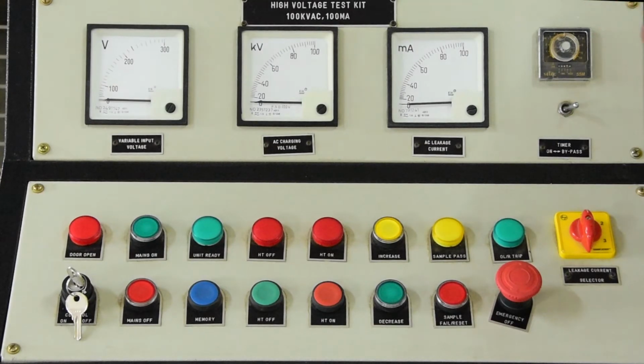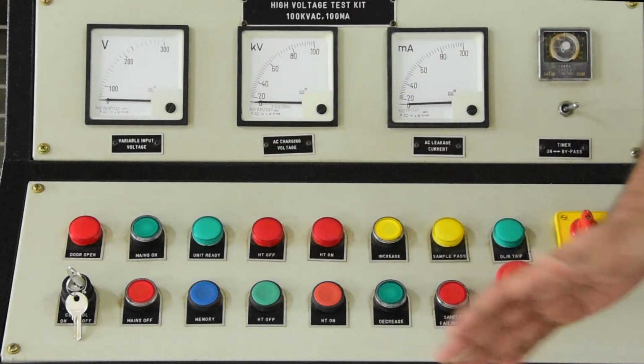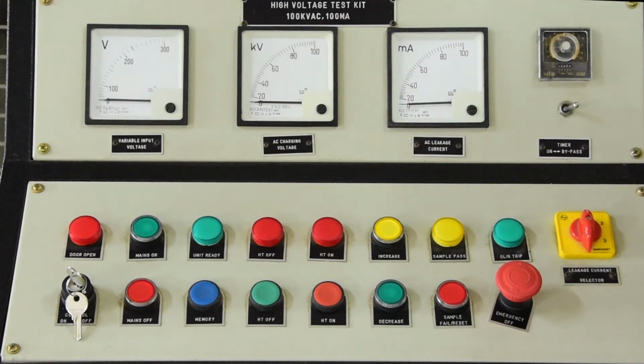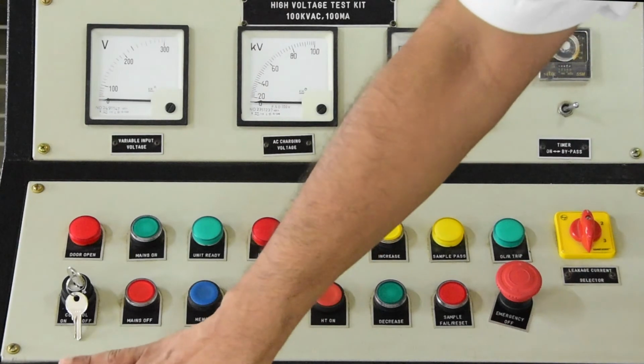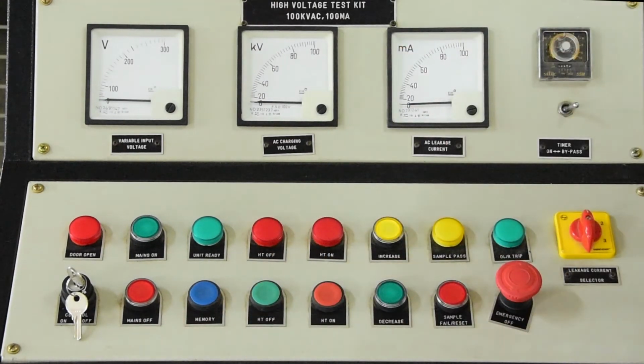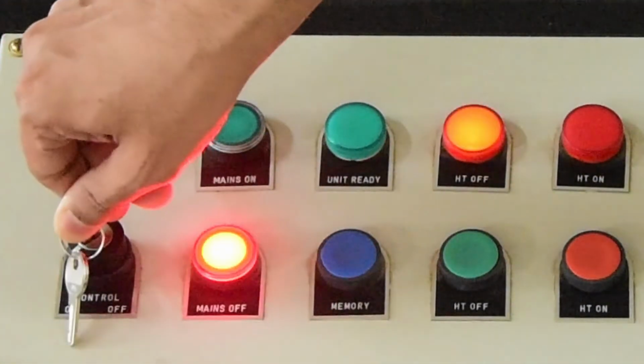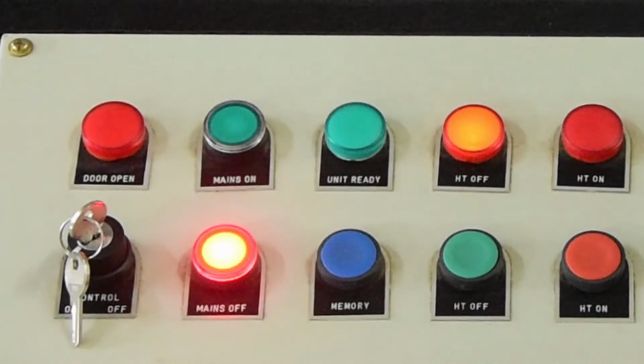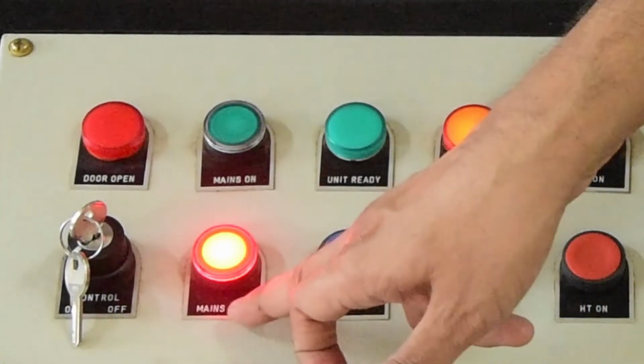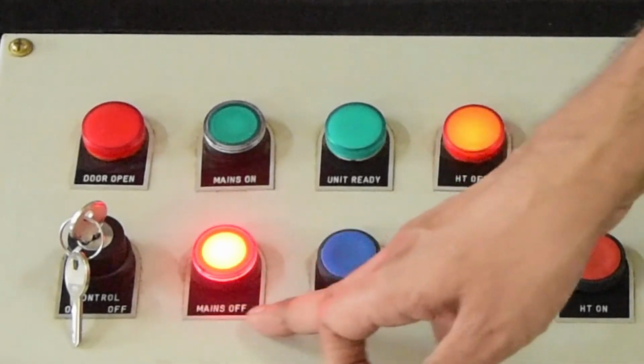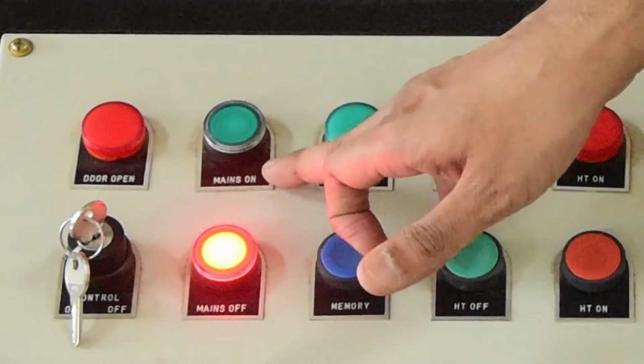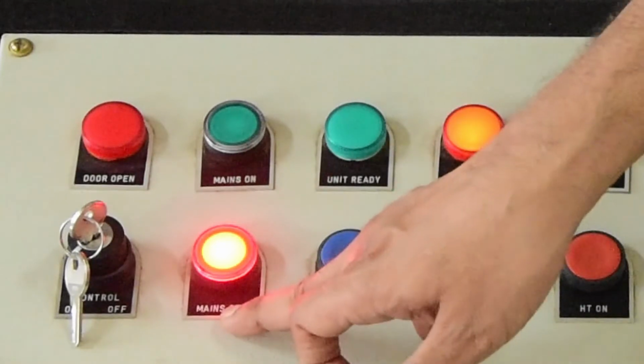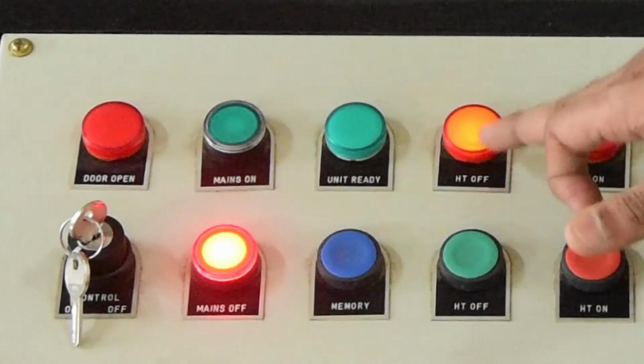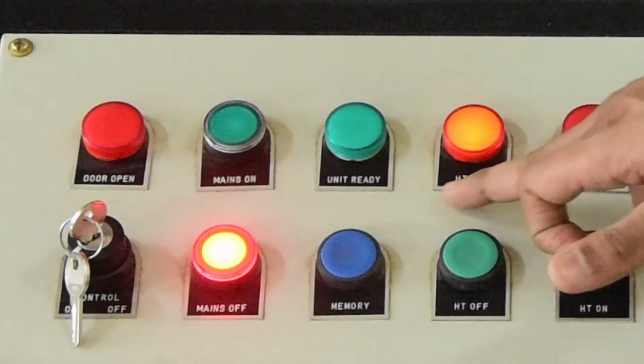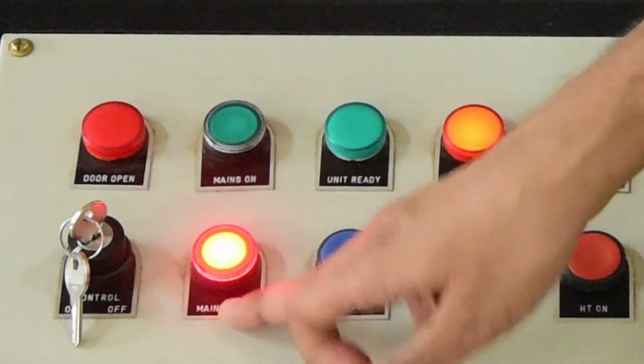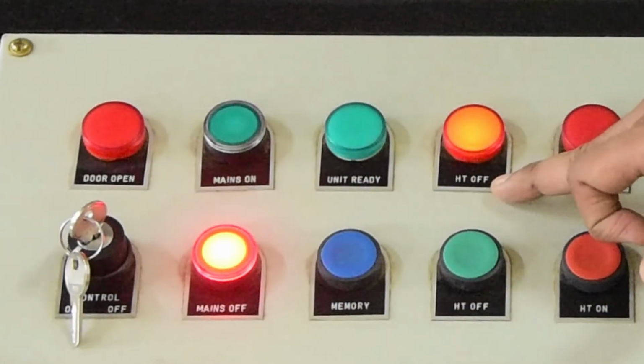Right, and now we are going to switch on the power supply. I'll just tell you, the procedure is very similar. First of all, the mains MCB switch is switched on, then the key is positioned to the on state. We can see a red lamp glowing. It's a mains off indication, which means we have not yet turned on the mains. Mains off, and at the same time this one is also glowing. This shows HT is off, mains is off, HT terminal output is off.